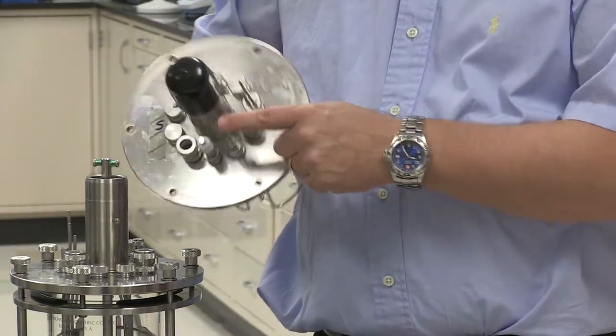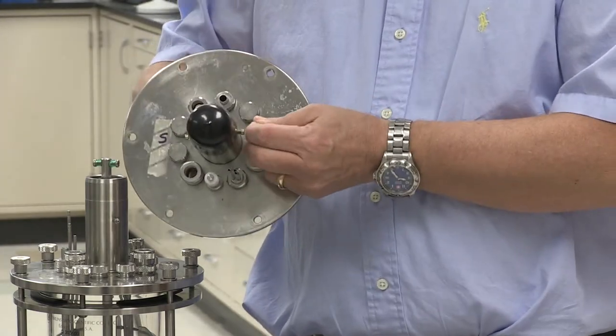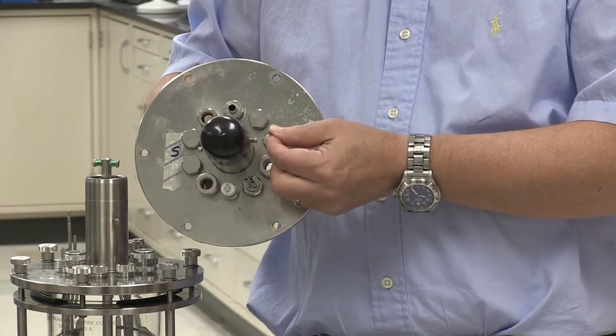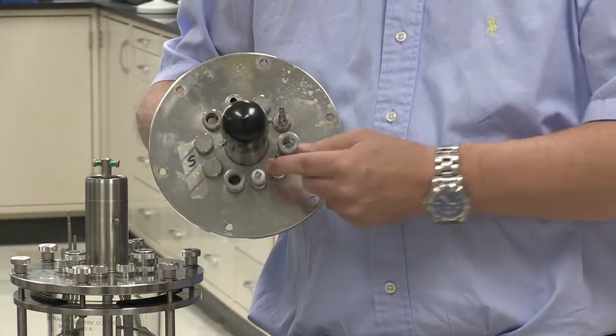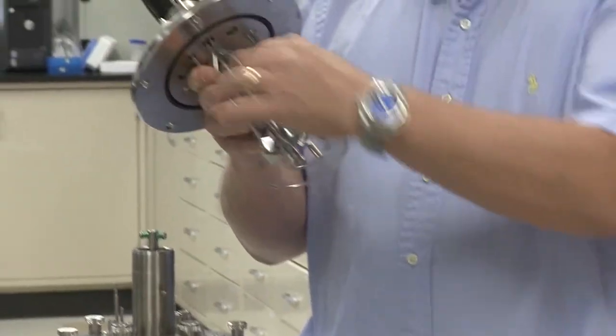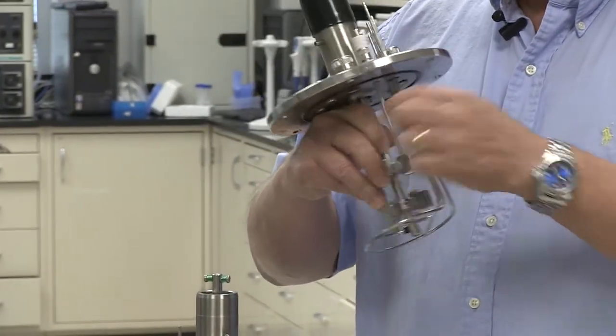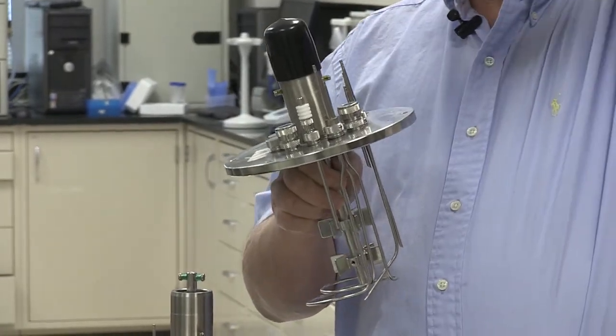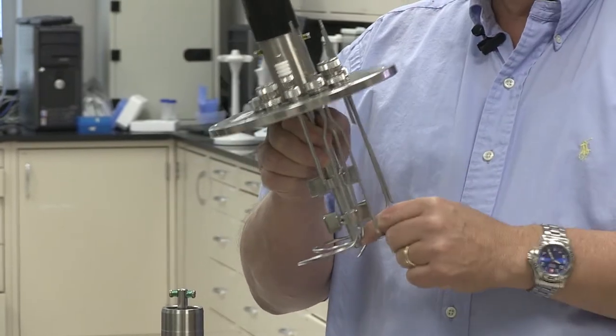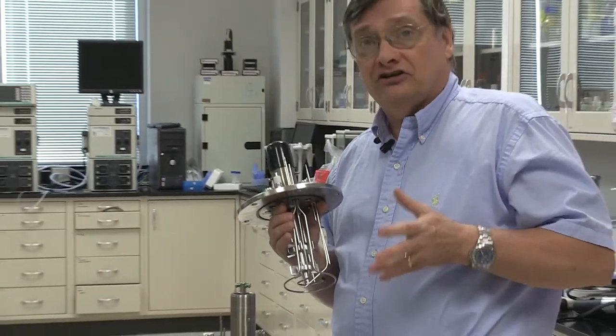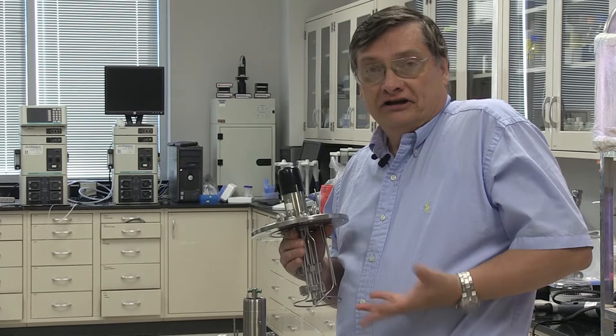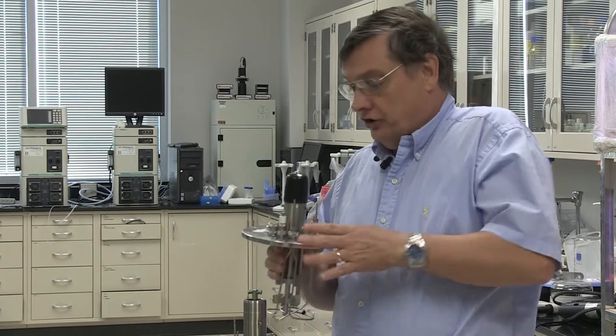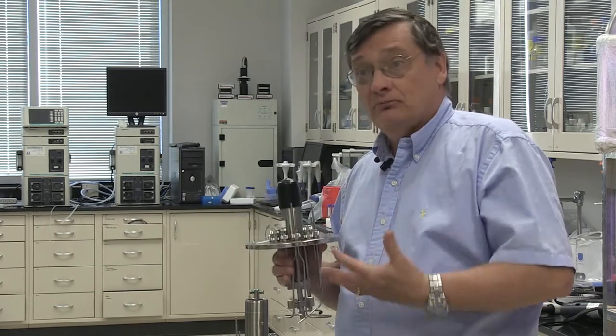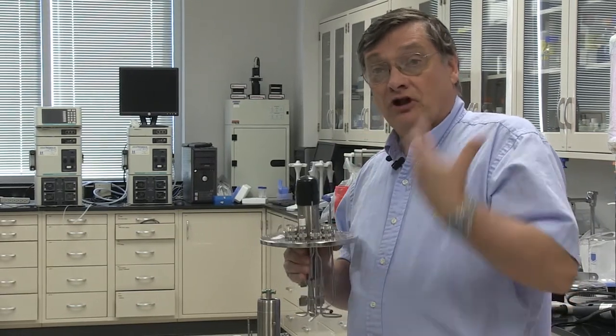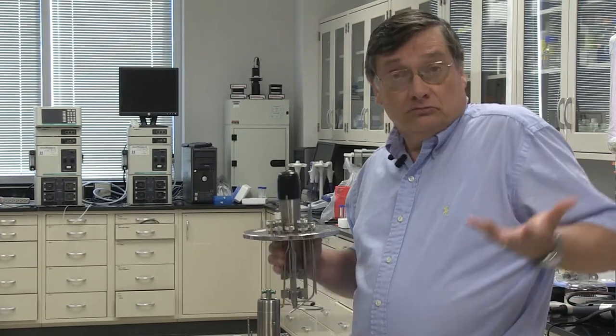So it has demonstrations of these different things. You'll see a couple of things on here where you'll see three small pieces of tubing or stainless steel tubing coming out. These are called triports because they have three connectors on them. You see they go through to the inside where there are different things that carry through. So this is a way of getting material from outside into the vessel. One thing I would like also to point out that I haven't already is that this is in order to grow the bacteria aseptically. That means that we don't want any other contaminants getting in. So all this will be assembled, the media will be placed in it, and it'll be sealed and autoclaved with the media in it, ready to go.